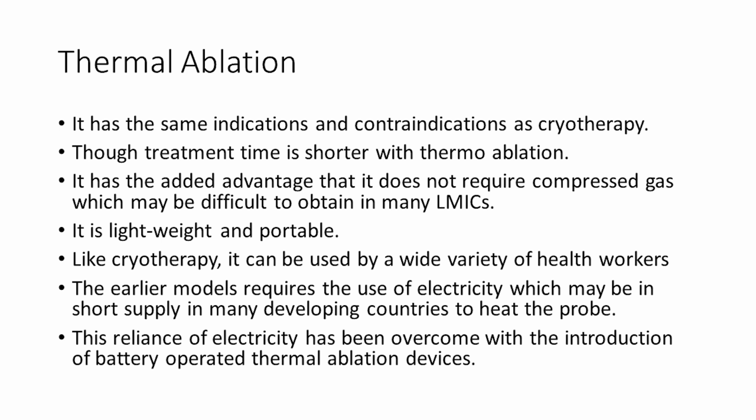Now, thermoablation has the advantage that it does not require compressed gas, which is difficult to obtain in many low- and middle-income countries. It's very lightweight and portable. It can be used by a wide variety of health workers. The earlier thermoablation devices used electricity, but currently a power bank or battery can be used to charge the device, so we don't need to use electricity for it.